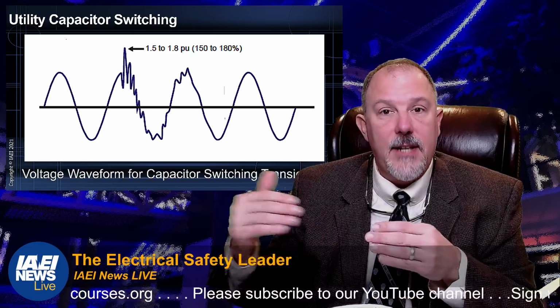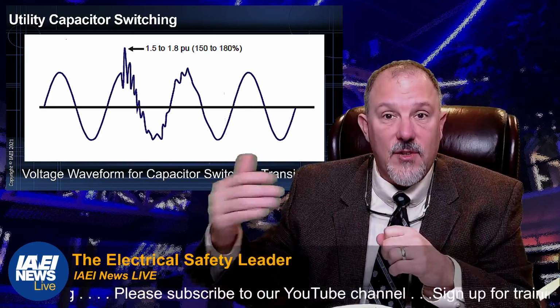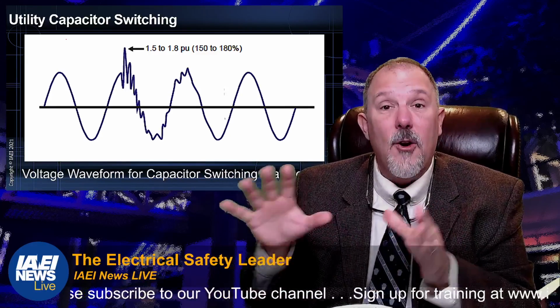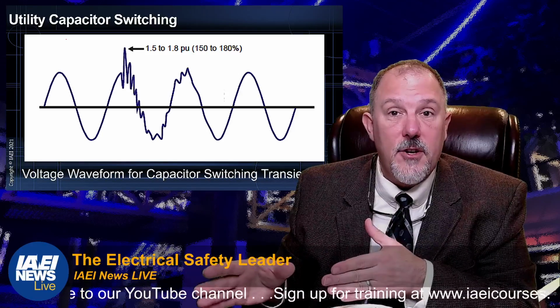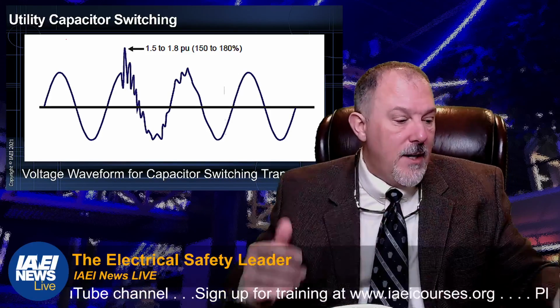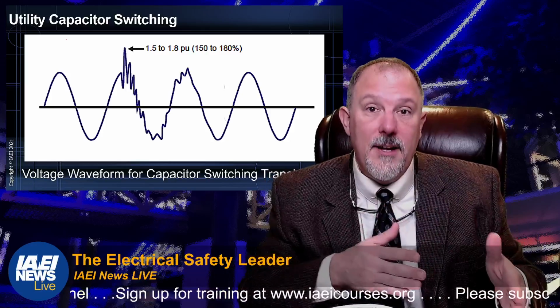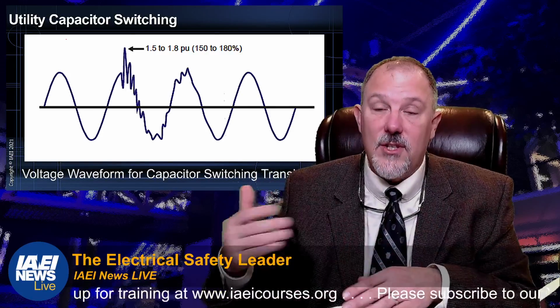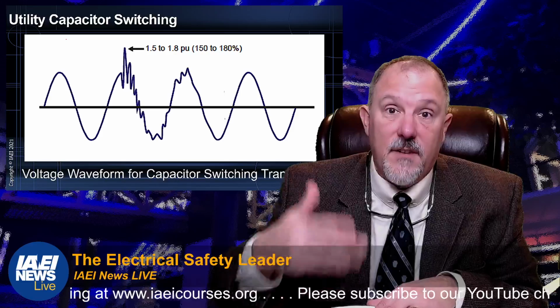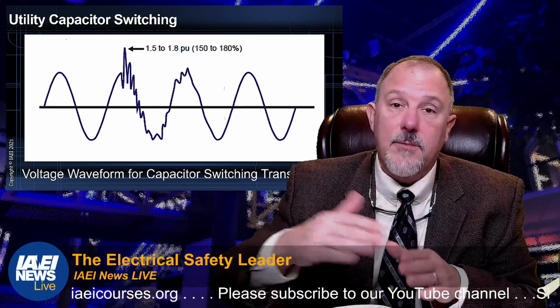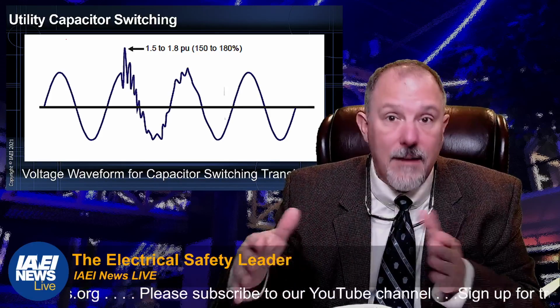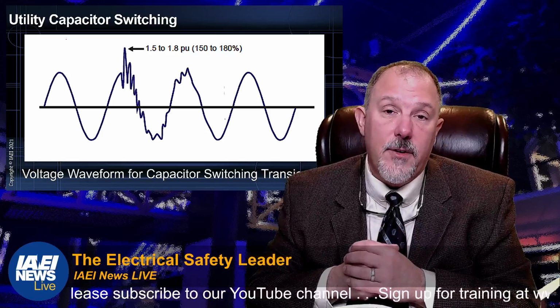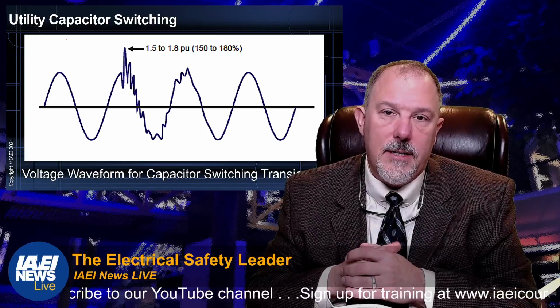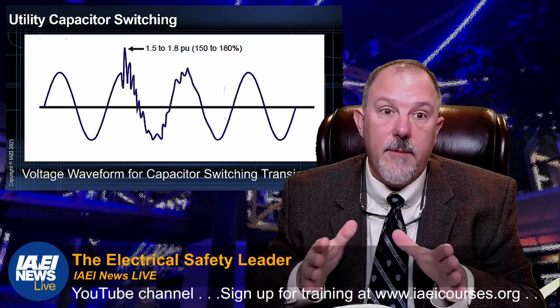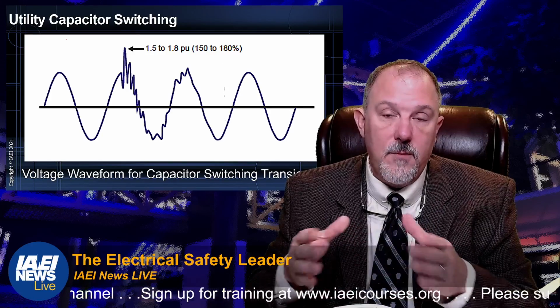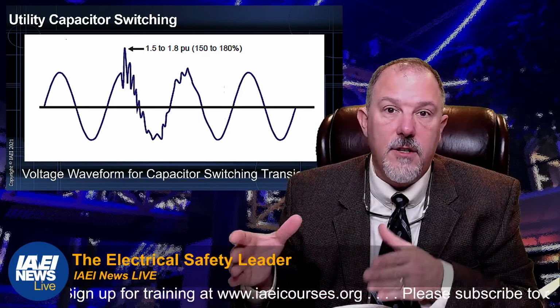So that drove a standards change, or discussions at the standards level, to say, where are you putting these? Where are you dumping these currents? Because you have the objectionable current rules within the National Electrical Code, and one could argue, is this an objectionable current? These events happen twice a day, and any surge event that would happen throughout the day was putting these transient currents on the equipment grounding conductor as well, and it was a real demonstration that this community needed surge protection because of these transient events.